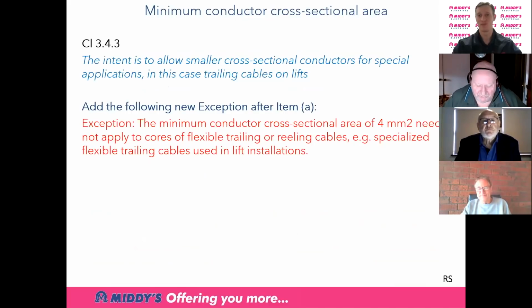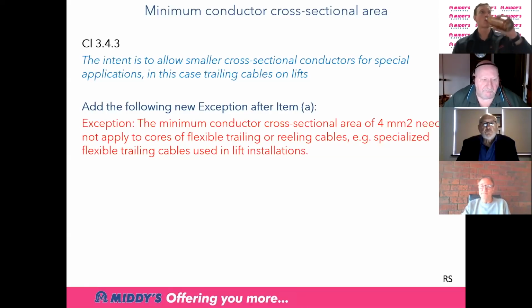We had some confusion within the industry regarding lift cabling. Some people call the lift cabling running up and down the lift shaft installation wiring. Some people called it the equipment wiring. And there was a bit of an issue in relation to them using 2.5 conductors and then paralleling them up as they needed to extend the length of them. So we've taken the easy option, and we've said that now any conductor under 4 mil associated with lift equipment can be paralleled. 2.5s can be. Thanks. Next slide. Thank you.